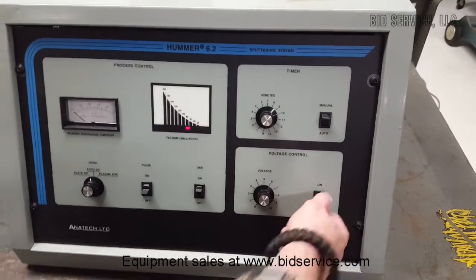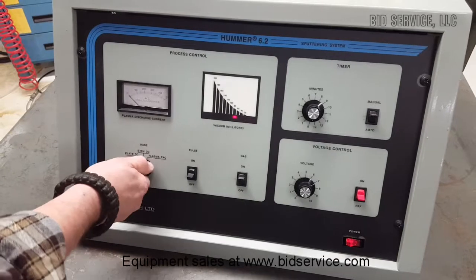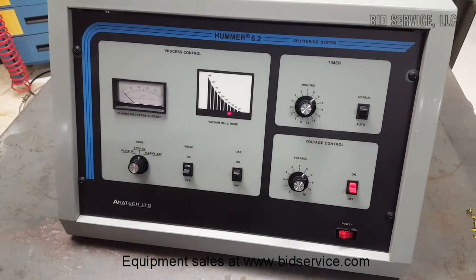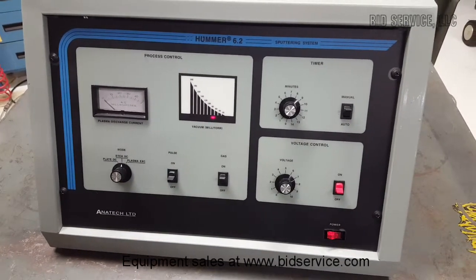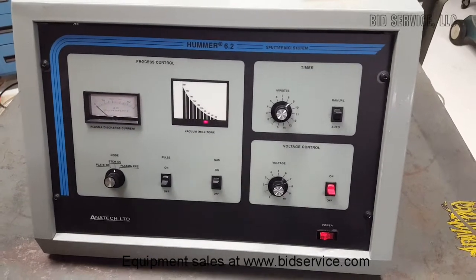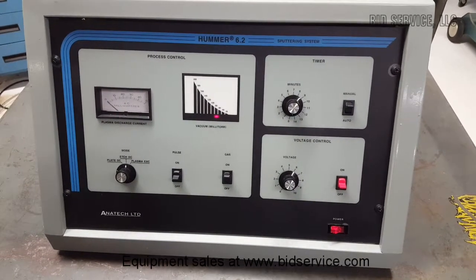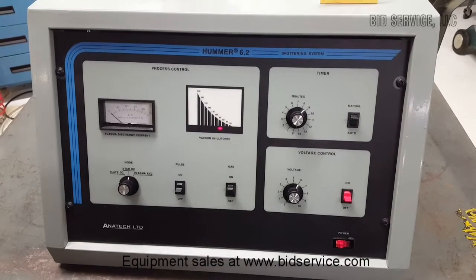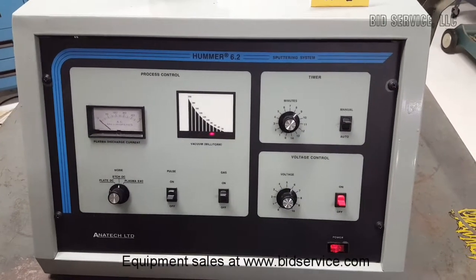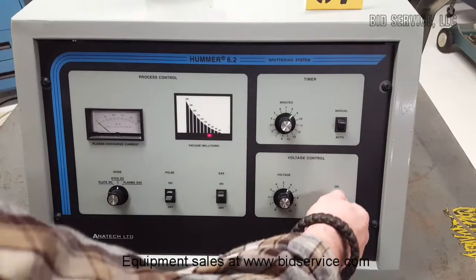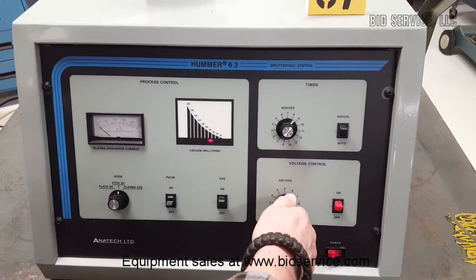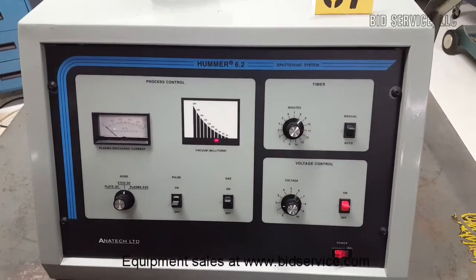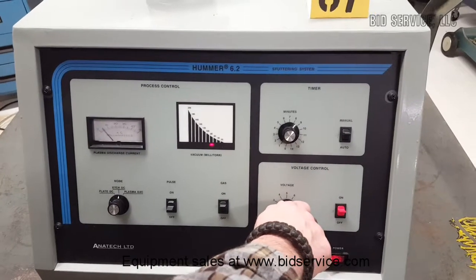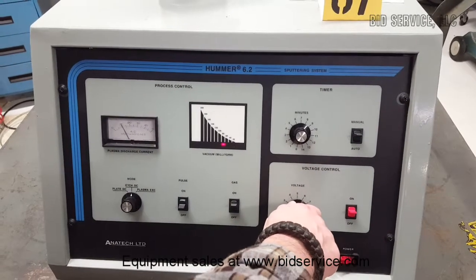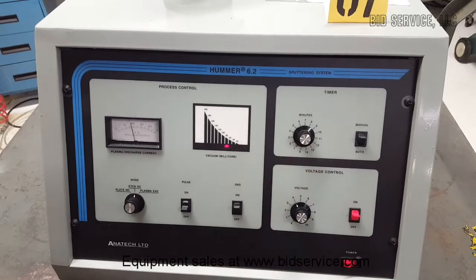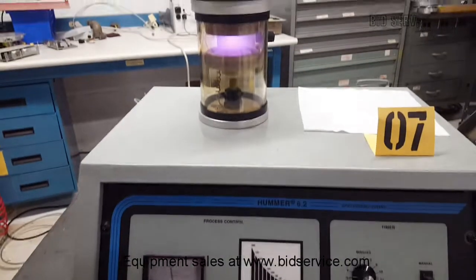For etching, it reverses the polarity so that anything on the stage will lose molecules to the etching ring. If you have gold or palladium or something exotic, make sure you remove that ring and replace it with the aluminum, otherwise you're going to be coating your ring. Once again, raise. For etching, the manufacturer recommends as high as 20 milliamps. You can see it's a nice healthy glow now, plasma.